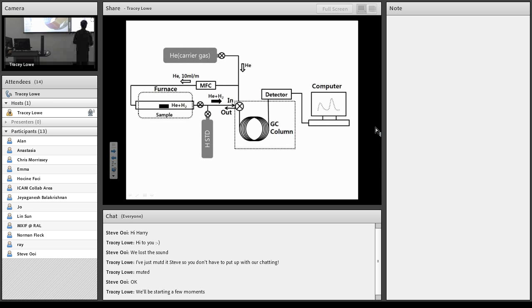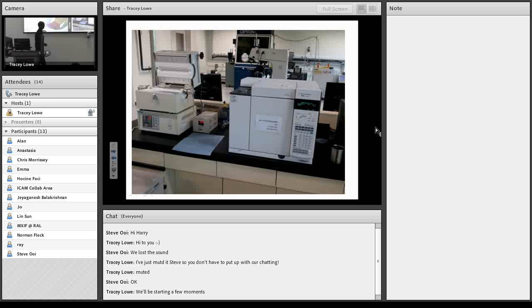So if your hydrogen is weakly trapped, then it will come out mostly at a low temperature. If it's strongly trapped, then it's pushed to higher temperatures. This is a slight oversimplification, because you can have several kinds of traps and your peak shape will be affected. You may not see separated peaks, just like in X-ray diffraction and so forth. And this is what the equipment looks like physically. This is your furnace, and this is the gas chromatograph, and there's a computer over there. So it's quite simple, but extremely accurate equipment. You're measuring in the carrier gas concentrations of 0.1 ppm or less of hydrogen in the helium gas.